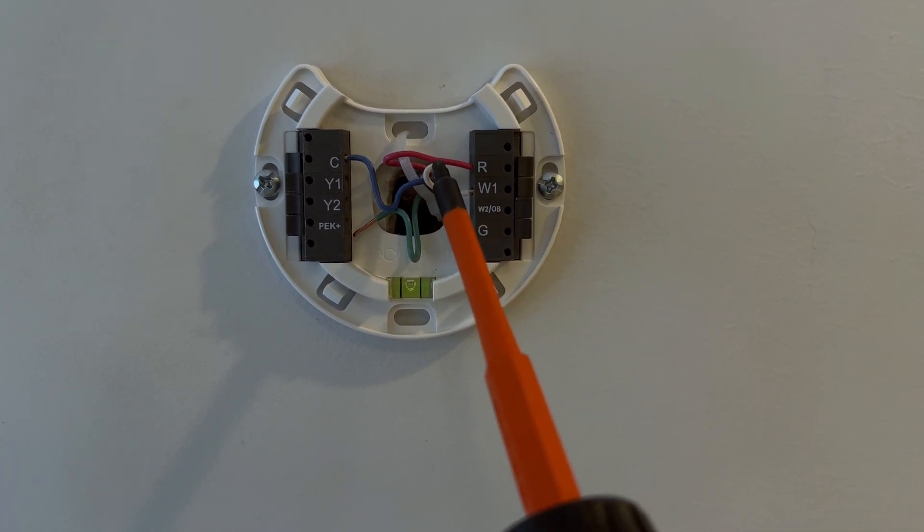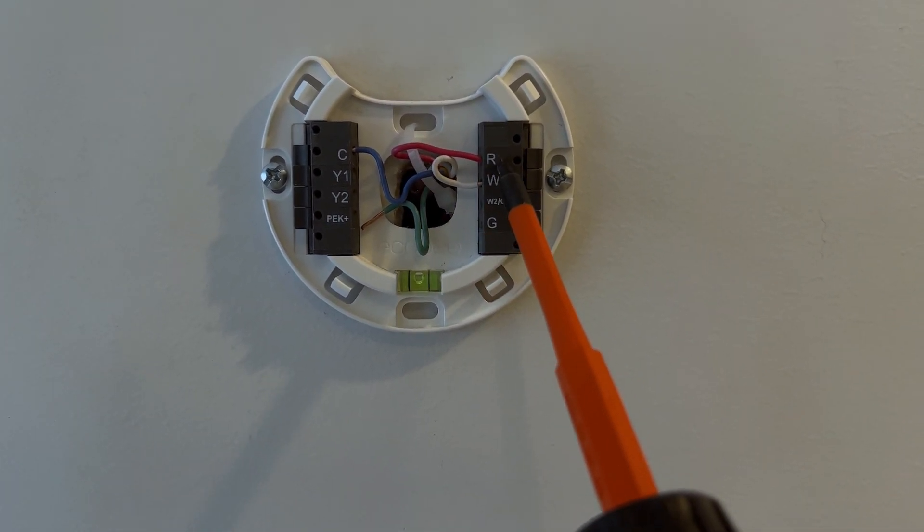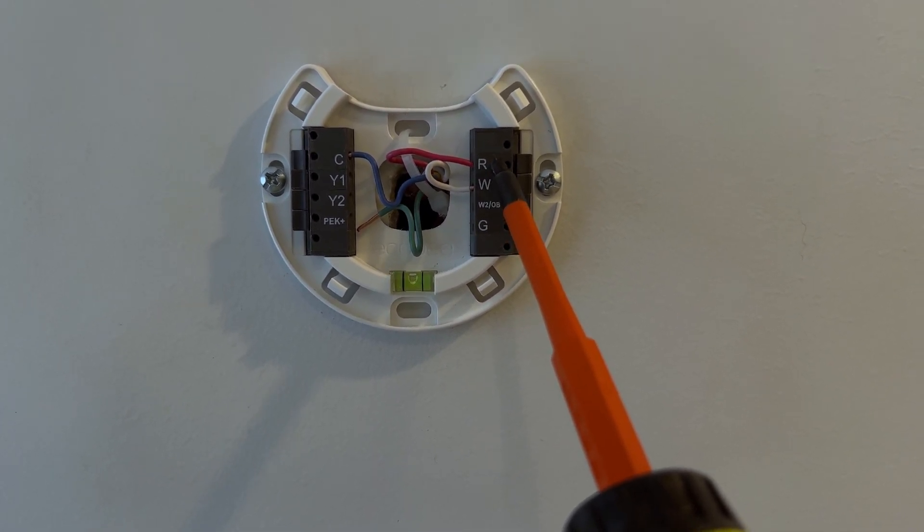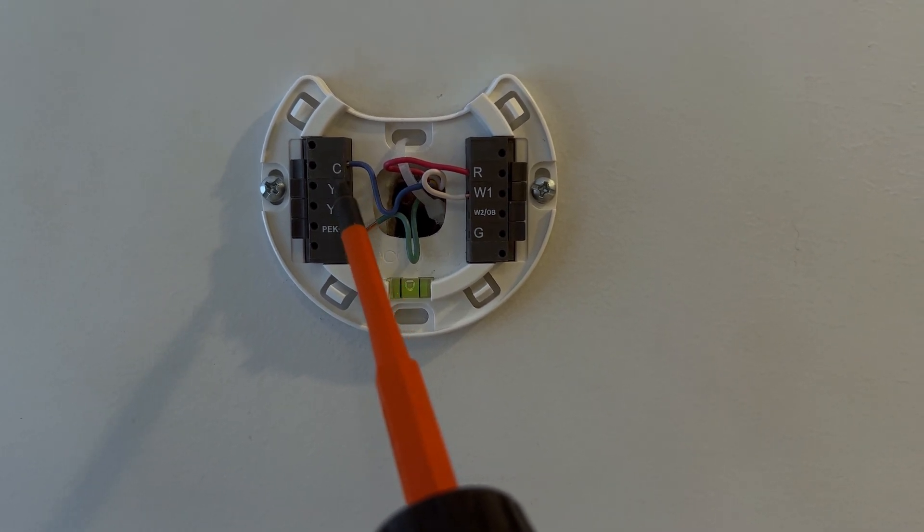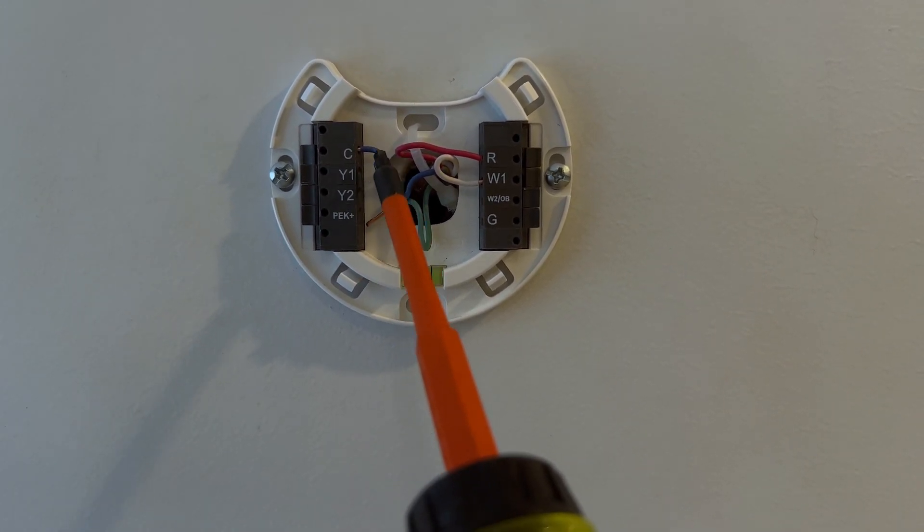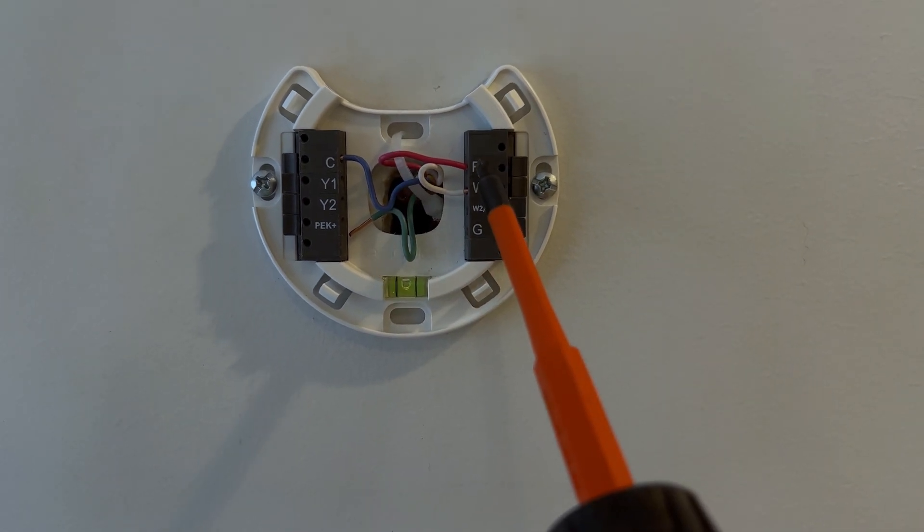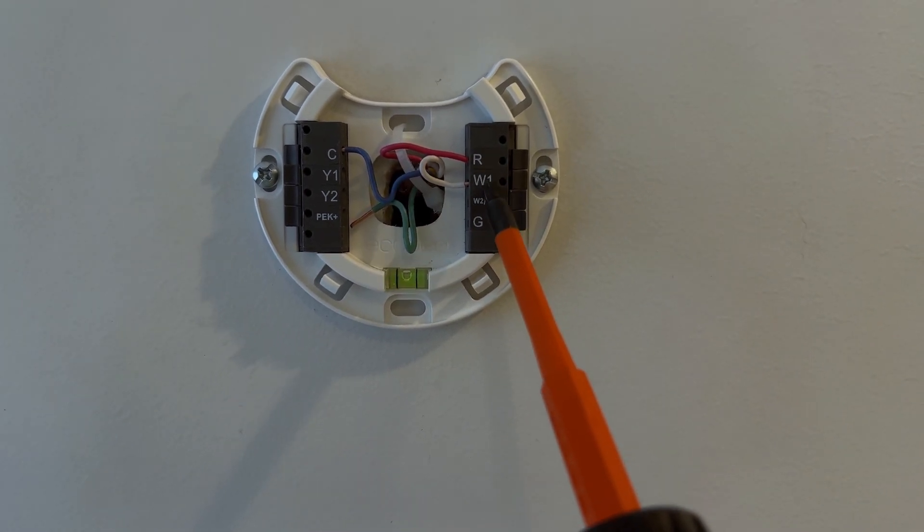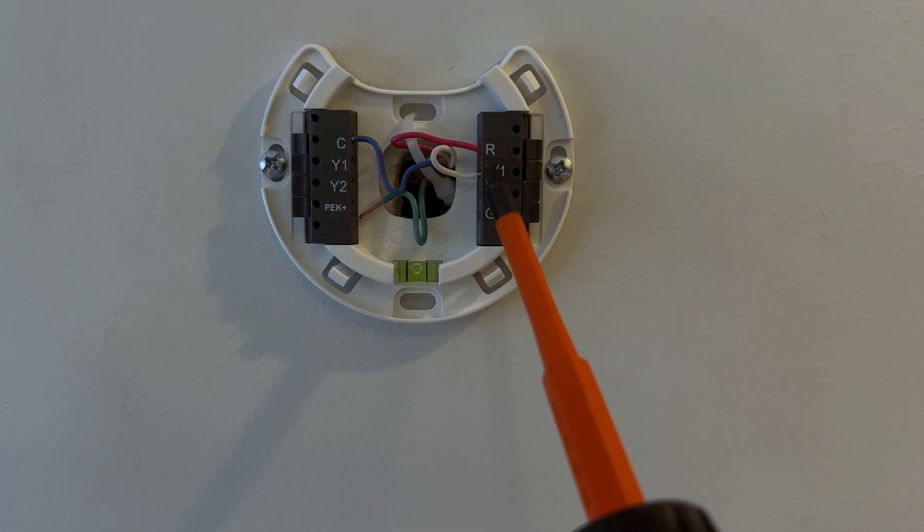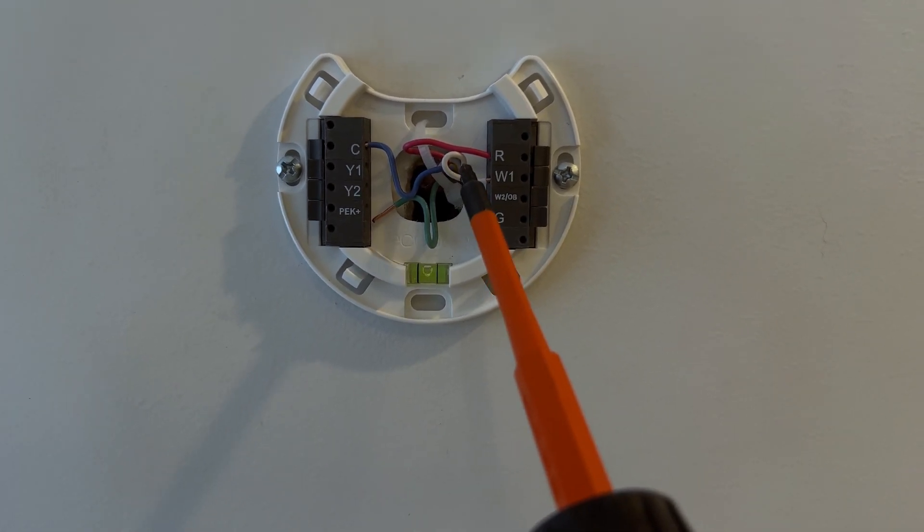And really it's very simple. The incoming power is red and that's on R. That's our 24 volt AC. The common wire is the other side of that power supply, and that is the blue. And then when the Ecobee calls for heat, it's just taking this red and it's energizing W, which is heat, and that's on the white wire.